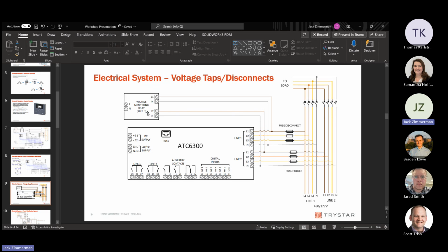We'll go into this next, the voltage monitoring relay setup over here, but this is probably the most complicated part of the system and the most involved for us. We have two lines of power that switch on and off, and our controller has to work in the worst case scenarios because that's what it's made for. It's to switch over when you have power quality issues, all of these different things.